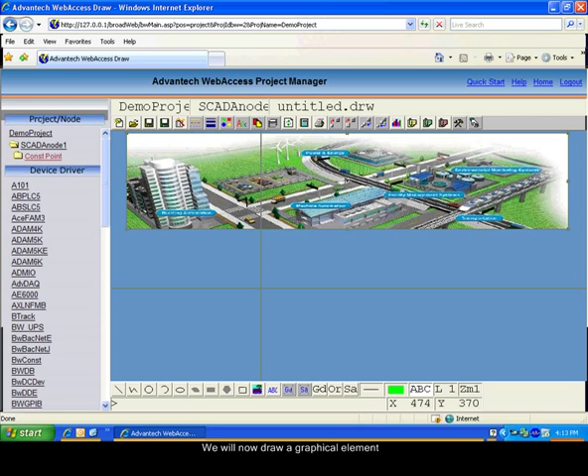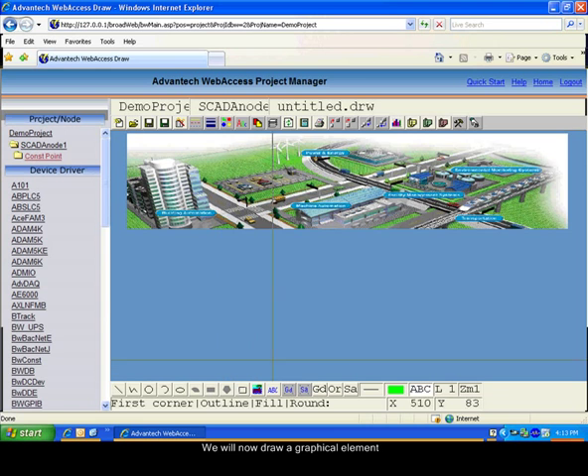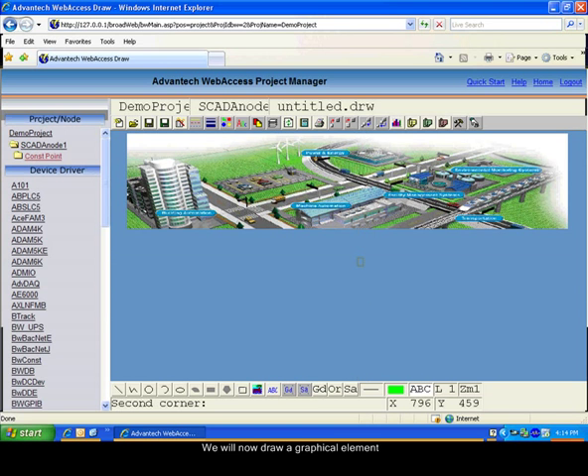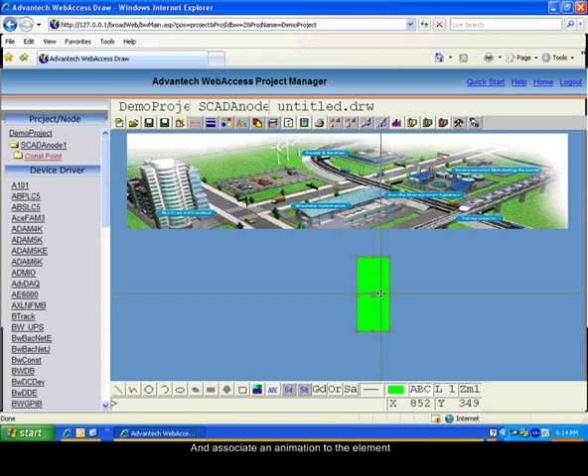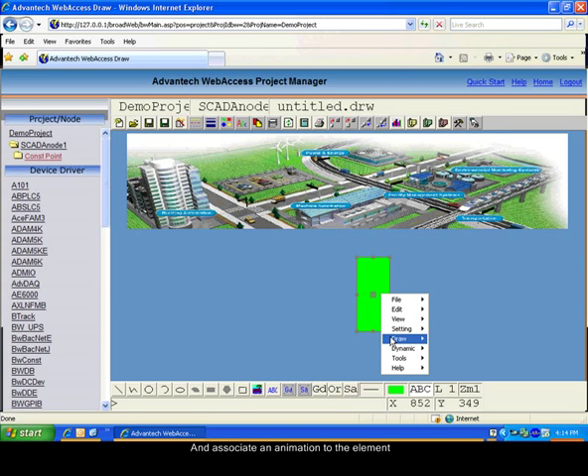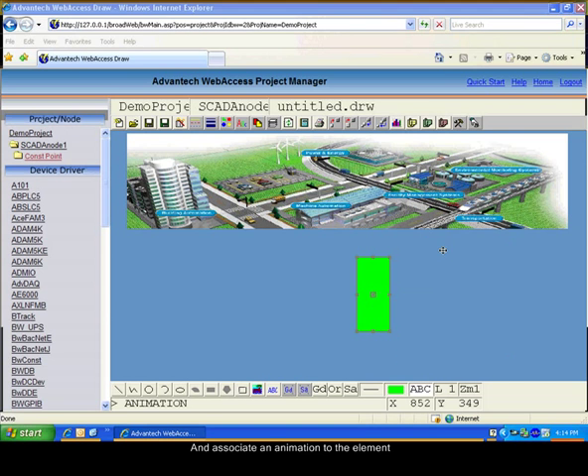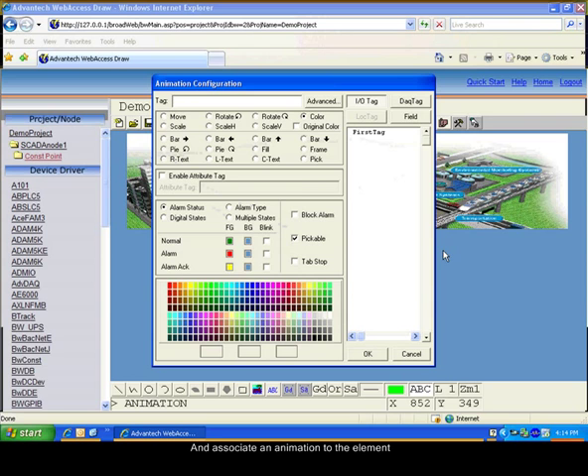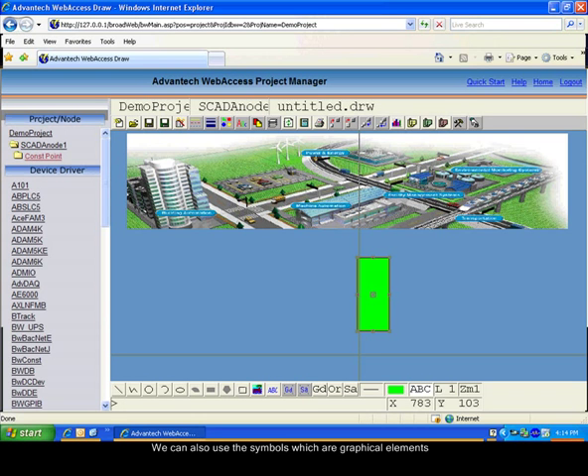We will now draw a graphical element, for example, a rectangle. We can add an animation to this rectangle by going into the dynamic animations. We will choose an animation where the rectangle will be filled depending on the value of the tag. Click on the tag to associate it to the animation.